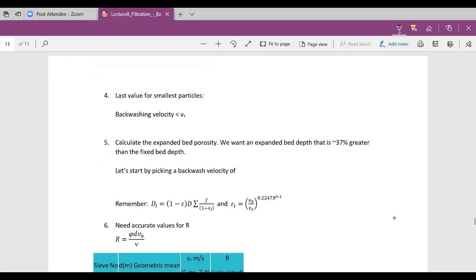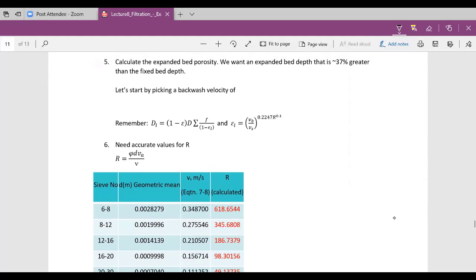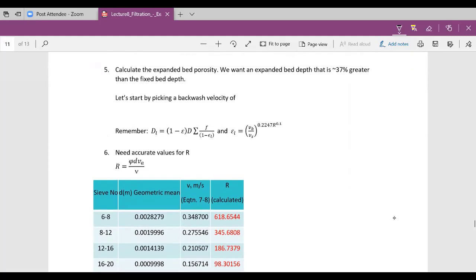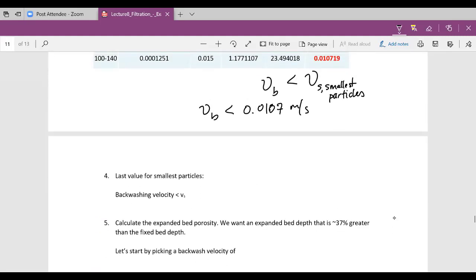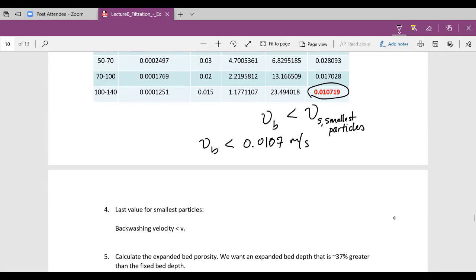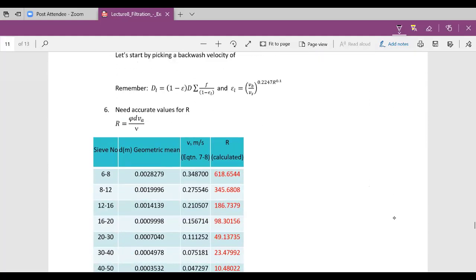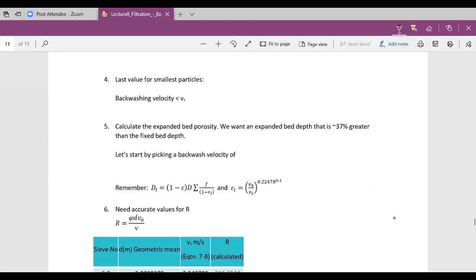What you then do is iterate on a solution — pick a backwash velocity. This backwash velocity must be less than 0.0107 meters per second, the terminal settling velocity of the smallest particles. When running these calculations in the Excel spreadsheet, if you get negative values, your backwash velocity is too high and you'll need to reduce it.